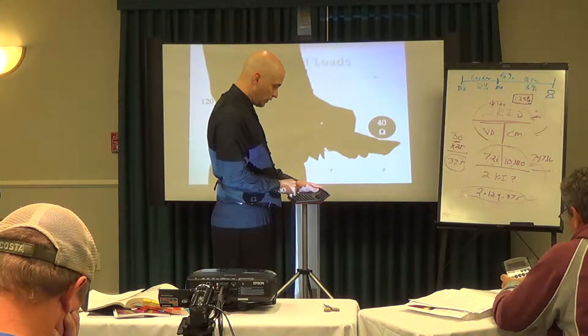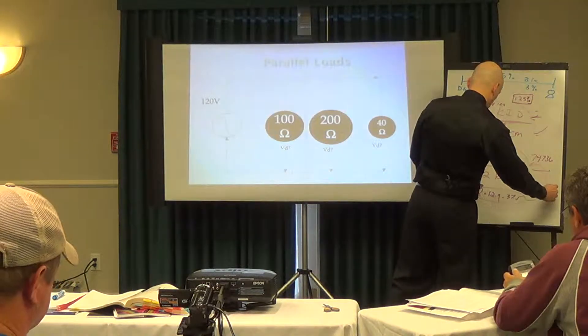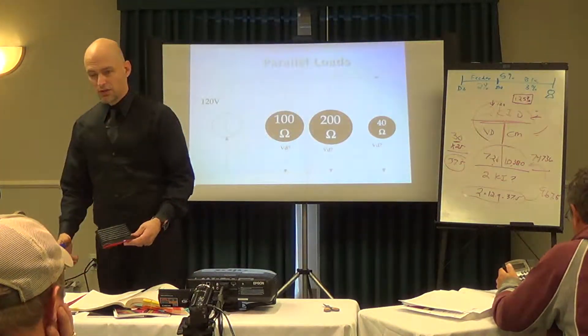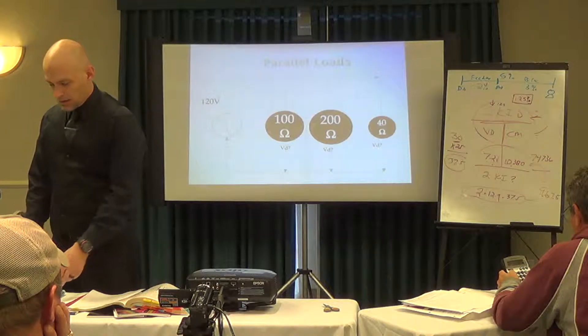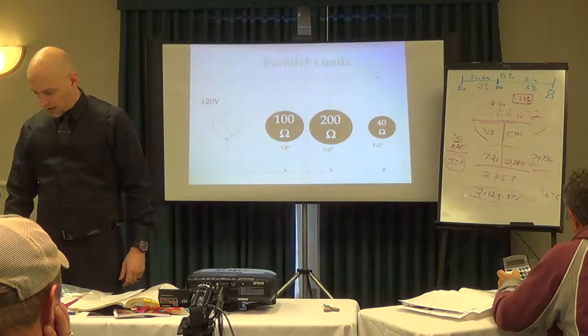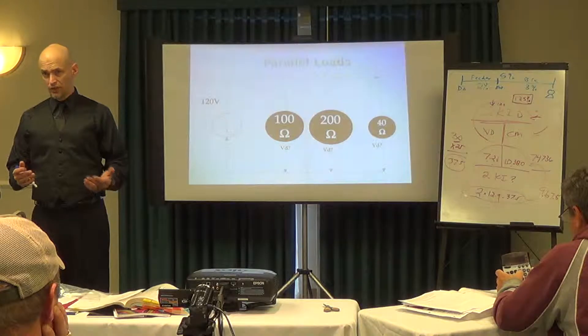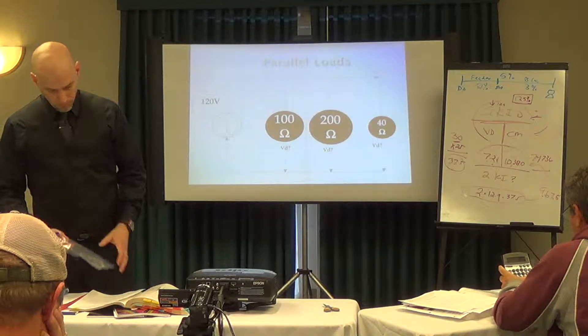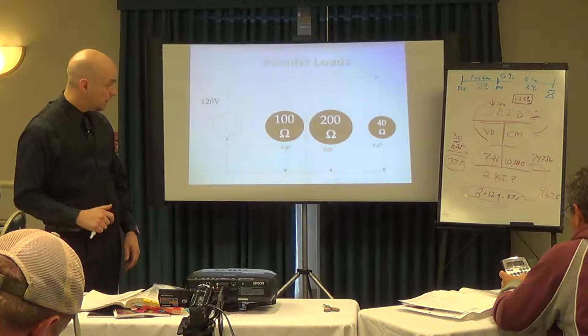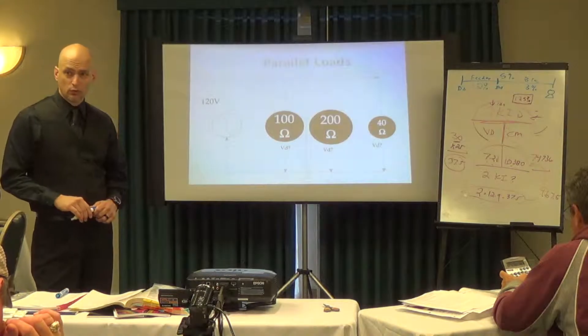Divided by or divided into what's the circular mils of number 10? 10,380. So these two numbers multiplied across. And in this block here, if you're looking for a bottom number, it's always divided into the top number. So 10,380 times 7.2 is 74,736. And divided by the bottom group there at 25.8 times 37.5. So 25.8, single phase of copper wire. 2 times 12.9 is going to be the same number in a lot of steps. So those two both might get us 25.8. That's something if you want to write that down. You can write 25.8 and 42.4 are the two more common calculations. Because if it's a single phase, it's going to be one of those two numbers.